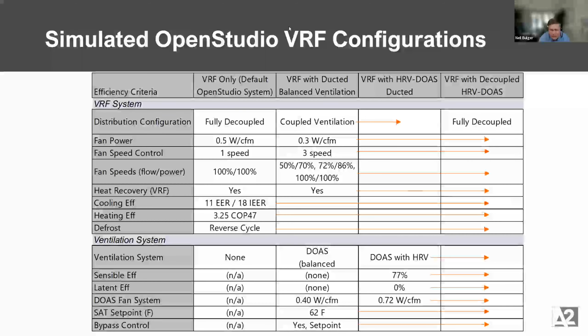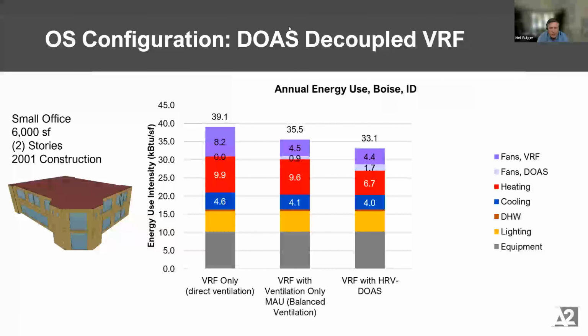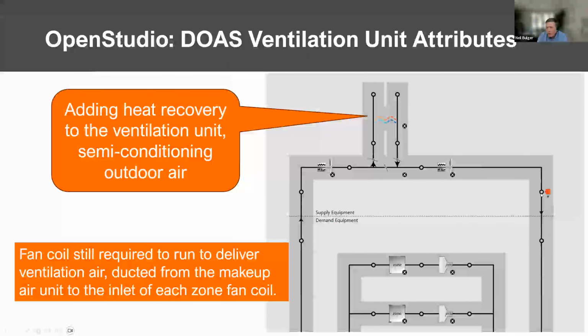So that's for the outside air. In the VRF system, you actually don't get the control in OpenStudio to dictate the supply temperature of the coils. So that input there is really to provide neutral air. You could definitely adjust it to be more seasonal, try and do a little bit of free cooling in the summer, a little more heat recovery in the winter. A lot of smaller HRVs and ERVs will have a very different range of options that you can do on DOAS control. So I would encourage it, but I would also not hold your breath that you're going to find a product that will give you amazing control of the DOAS.